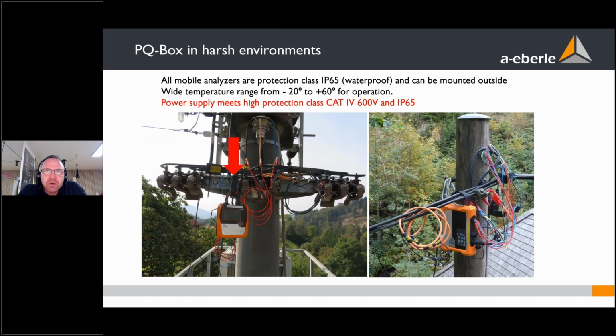Here are two pictures of outdoor installations. Often utilities install our analyzers outside in the field, here on a pole mount transformer. Here's a PQ-Box 100 installed. We connect directly here the voltage leads, where also the power supply is coming from, and the Rogowski coil. And we measure during heavy rains over weeks.